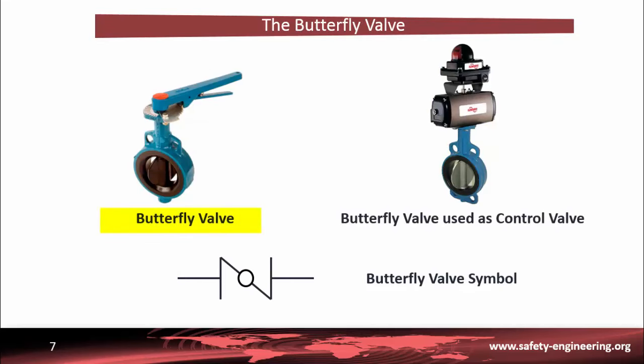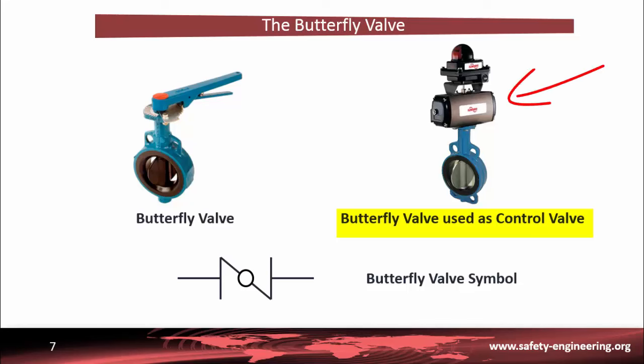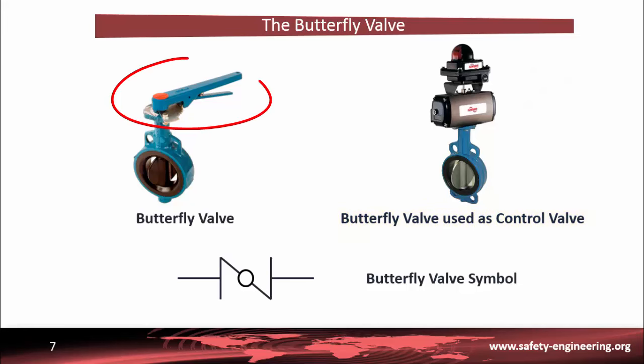A butterfly valve is a quarter-turn rotational motion valve used to stop, regulate, and start flow. Butterfly valves are easy and fast to open — a 90-degree rotation of the handle provides complete closure or opening of the valve. Large butterfly valves are usually equipped with a gearbox where the hand wheel is connected to the stem by gears. This simplifies operation but comes at the expense of speed. The valve plate, pivoted at the center and moved with the help of an actuator, looks like butterfly wings — hence the name butterfly valve. Butterfly control valves are best suited for regulating the flow of fluids. The actuator outside the valve can be fixed to an automatic or remote control mechanism to control the desired flow of the liquid.